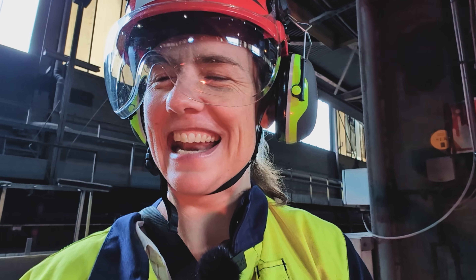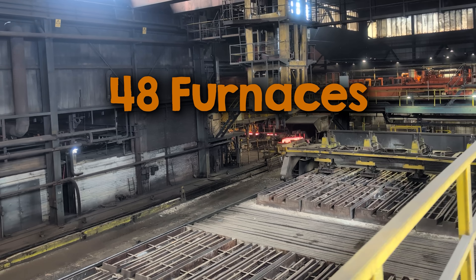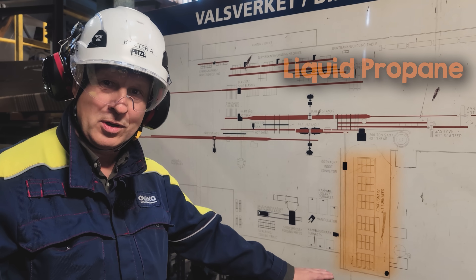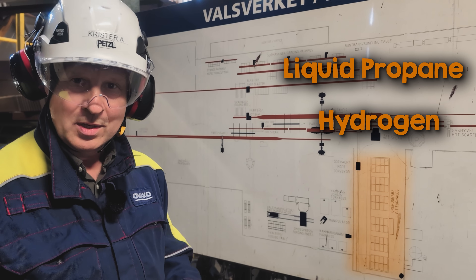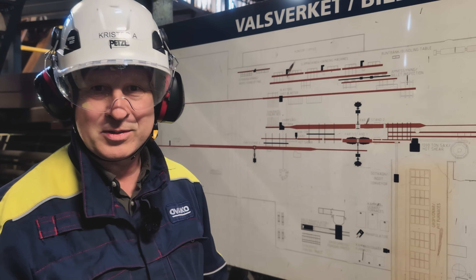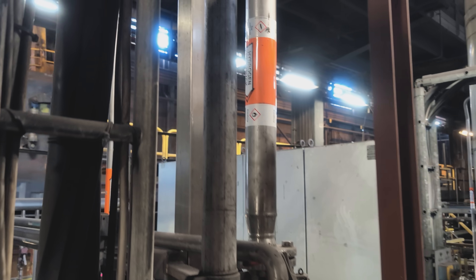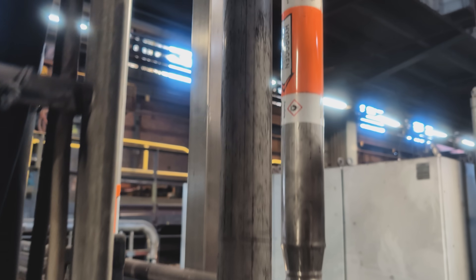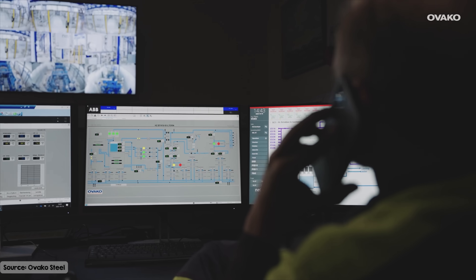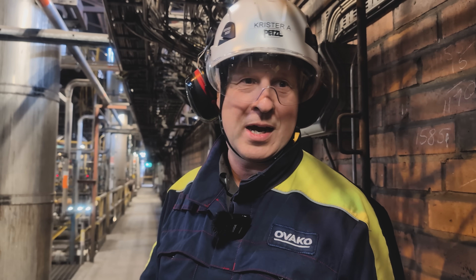The radiant heat is really something — it's 1,200 degrees down there. We have in total 48 reheating furnaces here, and we can keep six ingots in each furnace. They are heated by LPG or by hydrogen. We can use either fuel depending on conditions and the actual price of electricity and price of propane. In these two lines, we have two pipes in and distribution equipment to use both hydrogen or propane. A really intelligent software chooses the fuel depending on the temperature in the furnace and the availability of hydrogen from the hydrogen production.